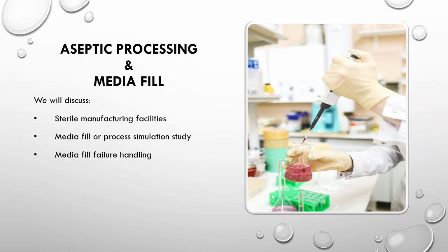Aseptic processing means manufacturing sterile medicines in a completely controlled clean room environment where every step is carefully designed to prevent contamination. For example, operators wear special sterile gowns, gloves, masks, and head covers, and the filling process is performed under laminar airflow to keep microorganisms away. But here is an interesting question. How do we know that the aseptic process is actually working properly? This is where media fill studies, also called process simulation studies, come into the picture.